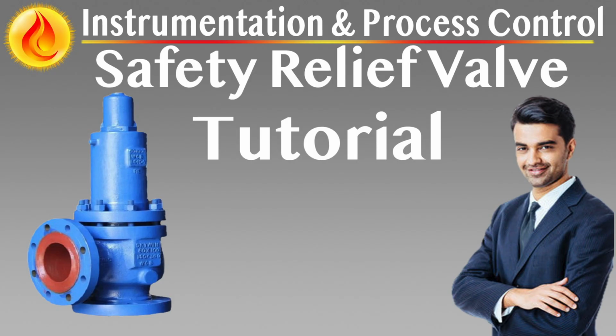Application scope. Mandatory in all blocked-in liquid piping systems where temperature rise is possible due to solar heating, exposed pipe runs, adjacent hot process lines, inadvertent equipment startup, typically used in pump discharge lines with isolation valves, heat exchanger bypasses, closed-loop utility systems, jacketed vessels and pipelines, serves local targeted protection rather than plant-wide safety relief.